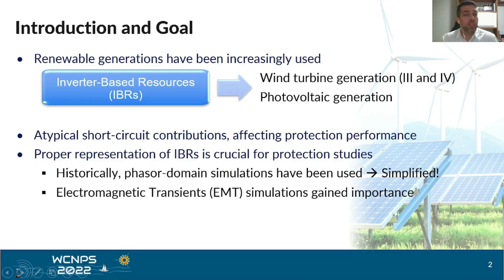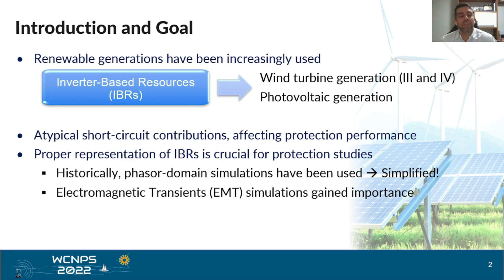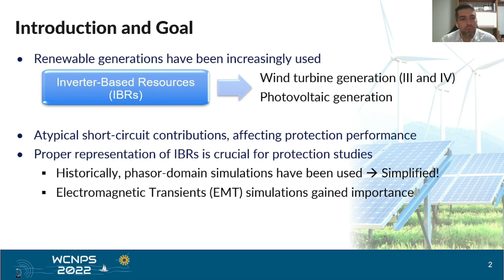It is well known that renewable generations have been increasingly used. In this context, Inverter-Based Resources, called here as IBRs, such as wind turbine generations of Type 3 and 4 and Photovoltaic Generations, stand out because they have resulted in atypical short-circuit contributions, and this atypical behavior has affected the protection performance. Thus, there are several professionals interested in properly representing IBRs for protection studies purposes.